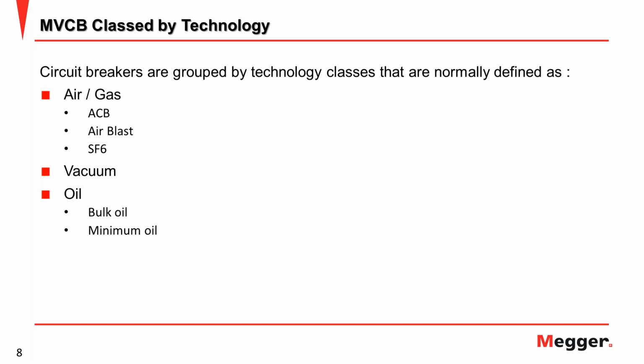And for vacuum, this vacuum breaker technology was introduced in, I think, 1960, a long time ago, but still exists until now with new development. So the vacuum circuit breaker is a circuit breaker where the arc quenching takes place in vacuum. They use the vacuum medium to extinguish the arcing between contacts inside the breaker.